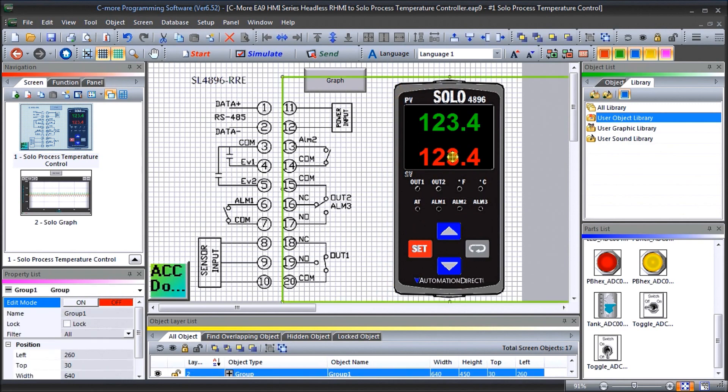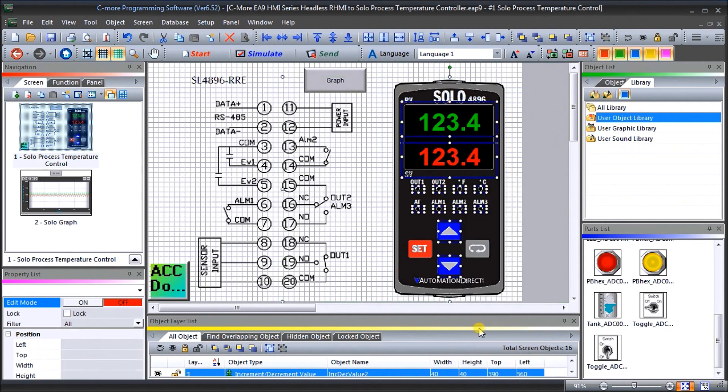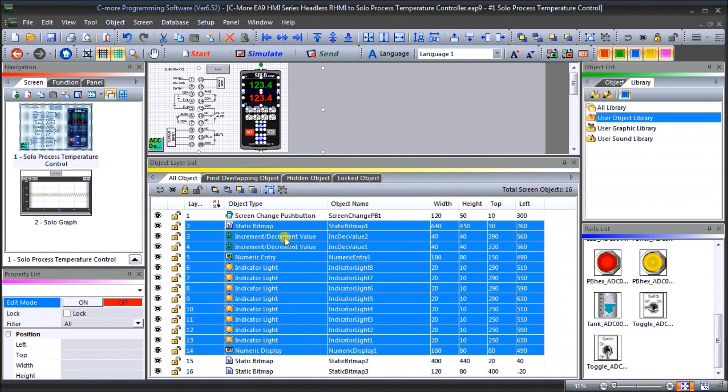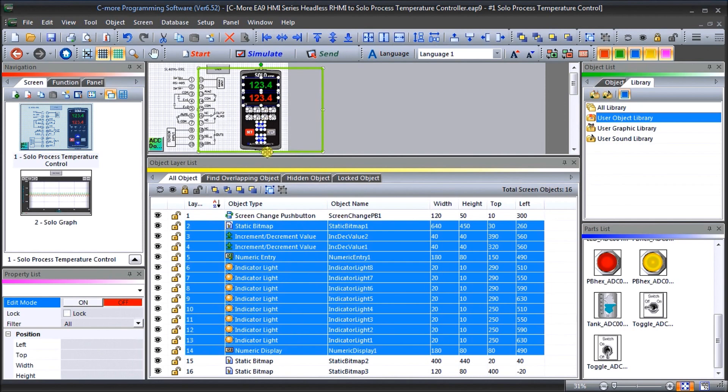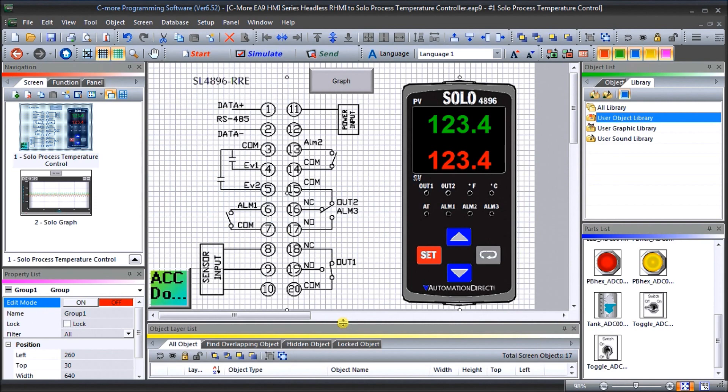When I ungroup that what happens is all of my different items that I've done or brought into that to make that picture comes up. So I have a static bitmap. I have an increment and decrement unit. I have a numeric entry that I have indicator lights and I have a numeric display. A numeric display is my present value. My numeric entry is my set value and I have my increment decrement which shows up and down which will automatically adjust that setting for me. And then I have my indicating lights and my indicating lights are all of my things like my outputs my degree C degree F that I want to show. So that's how I do that and then if I right click again I can hit group again and it groups it all back for me.